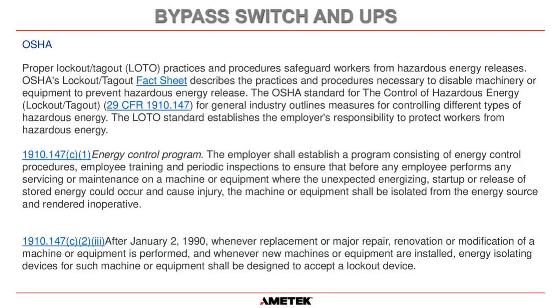And also, interestingly, in 1910.147(c)(2), it states that after January 2nd, 1990, whenever there is a replacement, major repair, renovation, or modification of a machine or equipment, then the new machine or any equipment installed should have an energy isolating device that can be locked out and can make that system fault-free. Now, obviously, that's open to interpretation in some respects, but basically what it's saying is you should be able to completely isolate your UPS after 1990.